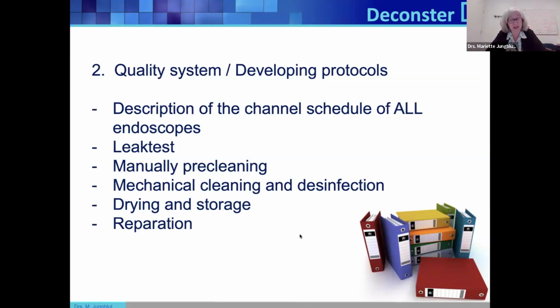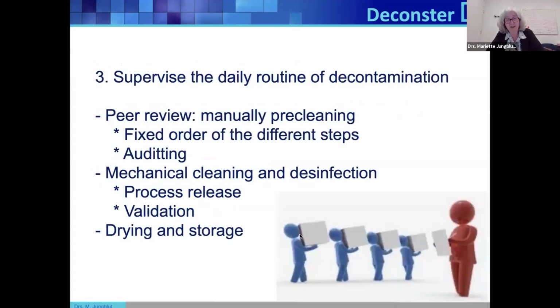Manual pre-cleaning directly after use, as soon as possible, after 5 minutes, after 20 minutes, but certainly not after 2 hours. If that happens again, we need a protocol on how to deal with it. Extensive soaking has to be in a protocol. Mechanical cleaning, disinfection, drying, storage, and then last but not least, again, the repair. Scopes are very difficult devices, they will break down.